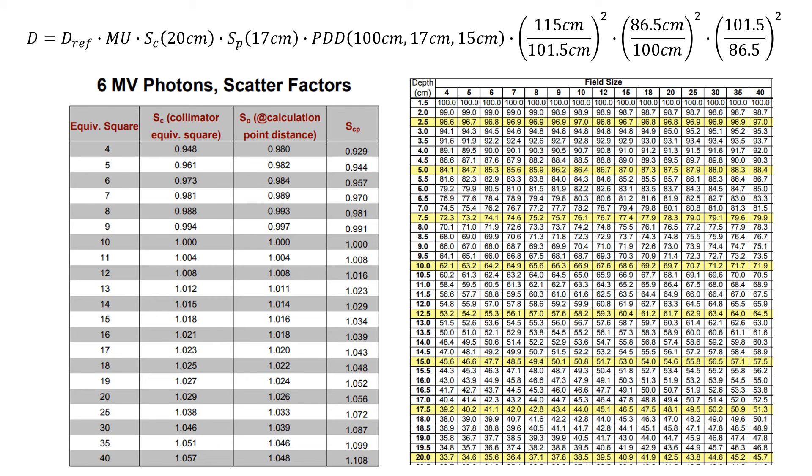And so we can just go ahead and look up our values here that we need. So for our scatter factors, we'll just find the collimator scatter factor for a 20 field size, the phantom scatter factor for a 17 field size, and then the PDD we will find for a field size of 17 and a depth of 15, and do a little bit of an interpolation there to get our values.